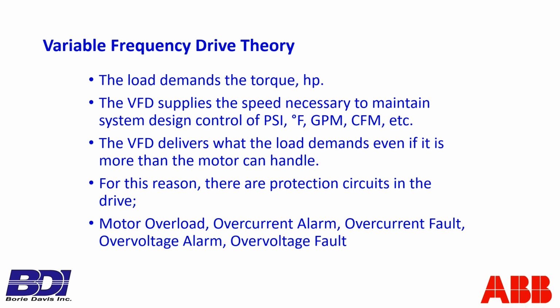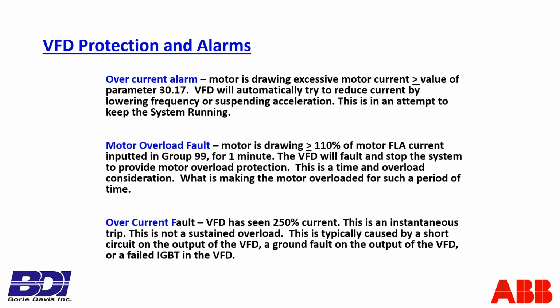There's a motor overload, overcurrent fault, overvoltage alarm, and overvoltage fault. Those are just a short list of them, but they're ones that I want you to understand so you know where to look to try and take care of them. The overcurrent alarm is not a shutdown. It's a statement of we're seeing too much motor amps being drawn, and we want to keep the application running. So what could be causing this event to occur?